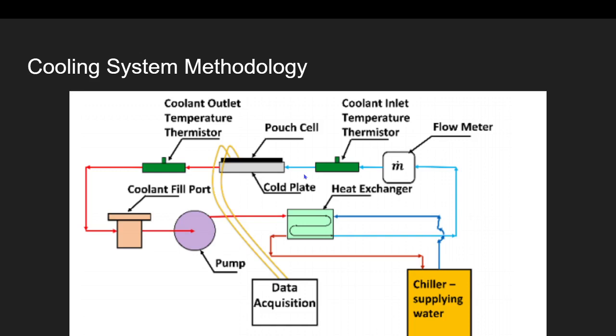So the way this cooling system is going to work is we are going to have a chiller which supplies cool liquid to the heat exchanger, which then exchanges that with the coolant fluid. This is pumped by the pump, as you can see here, which then goes to a mass flow meter to determine what the flow rate is, how much liquid is moving to the cooling system. Next, we're going to measure the temperature before the cell. It goes through the cold plate, where it's removing heat from the cell. Then we're going to measure it after the cell. It's then going to repeat this cycle over and over again.